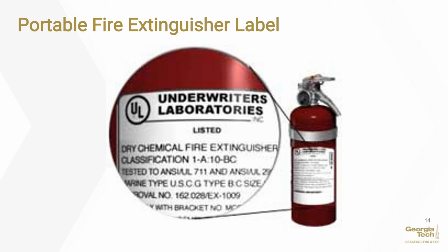Let's take a look at the label pictured. The classification is 1A:10BC. The letters A, B, and C represent the types of fire for which the extinguisher has been approved. The number in front of the A rating indicates how much water the extinguisher is equal to and represents 1.25 gallons of water for every unit of 1. For example, a 4A rated extinguisher would be equal to 5, or 4 times 1.25, gallons of water.